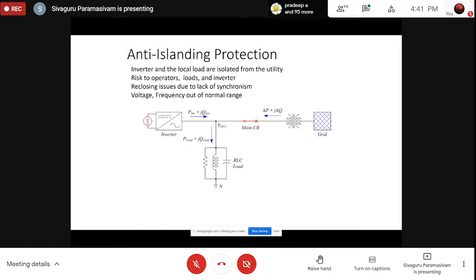That's why in some of the systems, wherever the island function is not approved, we should have anti-islanding protection, which means a part of the inverter's control system should detect the failure of the grid. Within no time, it should disconnect itself from giving the power back to the grid.